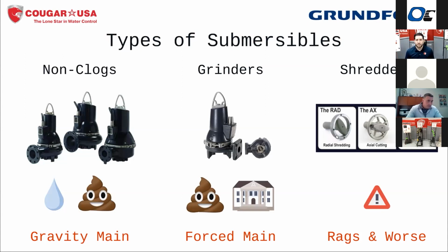So these are actually inside a submersible pump. Or Grundfos has the offering of the sewer chewer, which is a grinder that goes on the inlet side of the basin and basically can cut up everything as it goes into the pit. And then you can use normal non-clogs after that. So there are some other options for really bad pits like that where you are having issues wearing out the cutting wheels. But I think any sort of cutting wheel is going to be a concern at some point, or a point for maintenance. So good question.